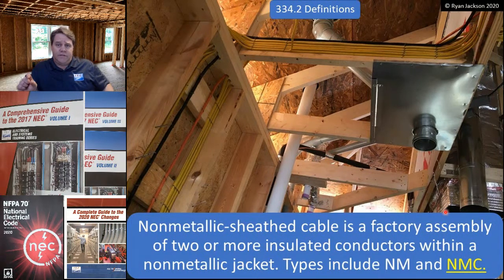Now, I underlined and have yellow text under NMC, which is showing a 2020 code change. Not that we added NMC, but we actually deleted a type of NM cable called NMS. So right now, NM cable is the NM cable that we all know and love. And I try to not say trade terms, but I'm just going to go ahead and say it, Romex, right? NM cable is Romex, and that's a registered trademark of Southwire, so I try not to say that. NMC is a corrosion-resistant version of NM cable, hence the C: nonmetallic sheathed cable, corrosion-resistant.